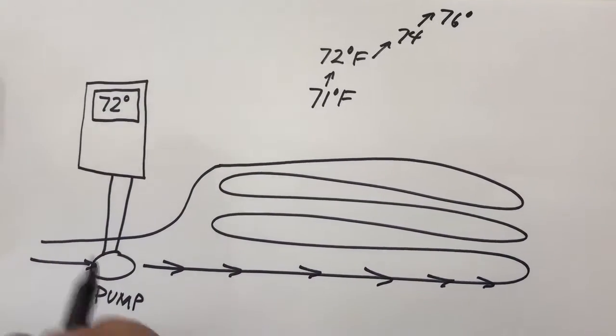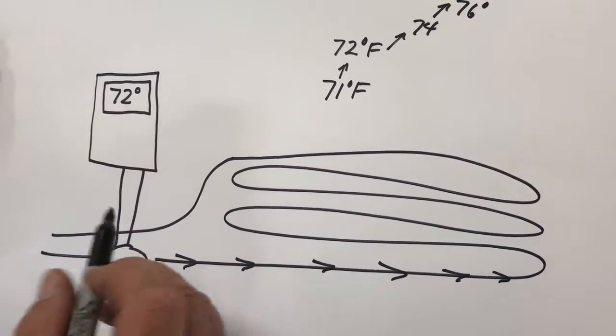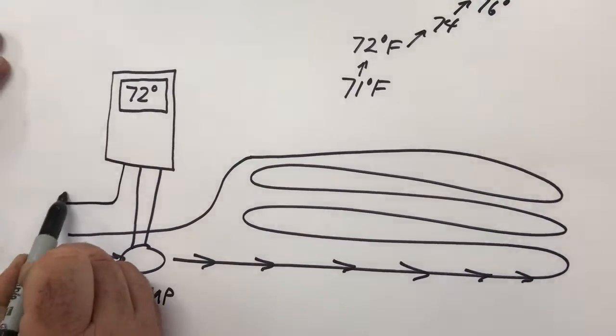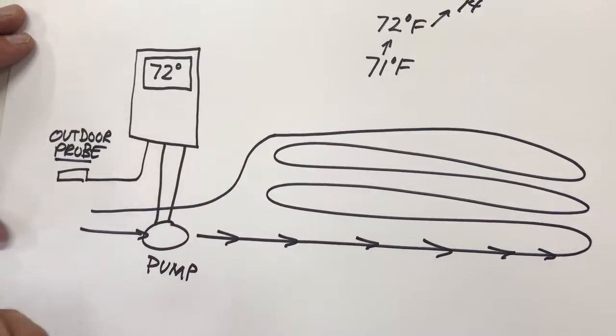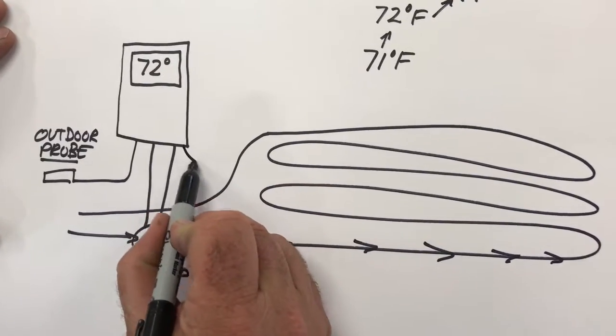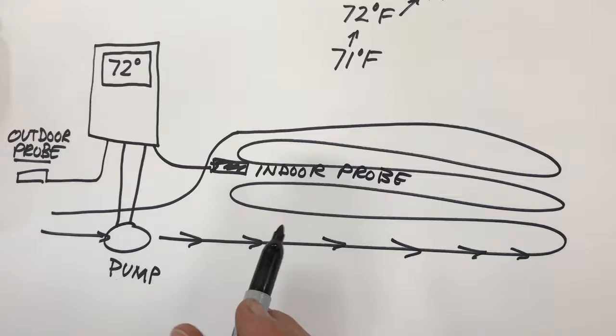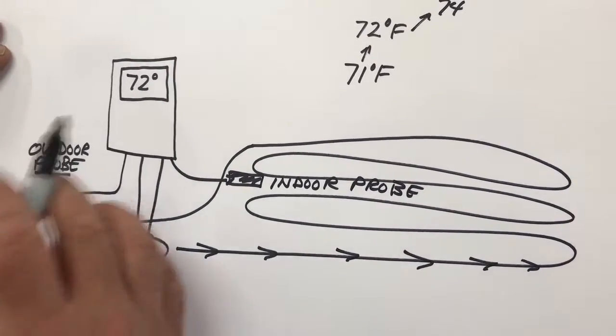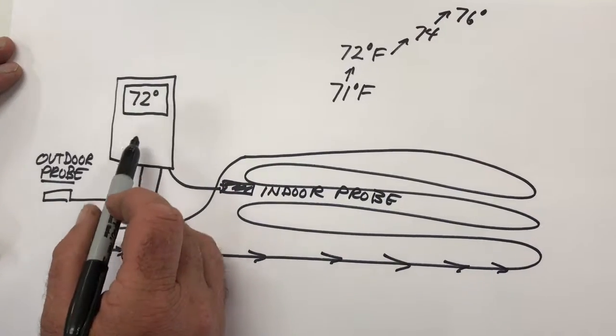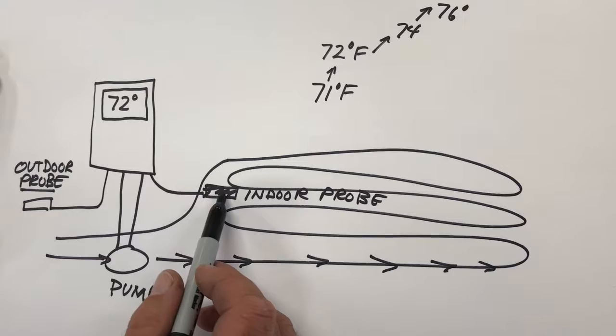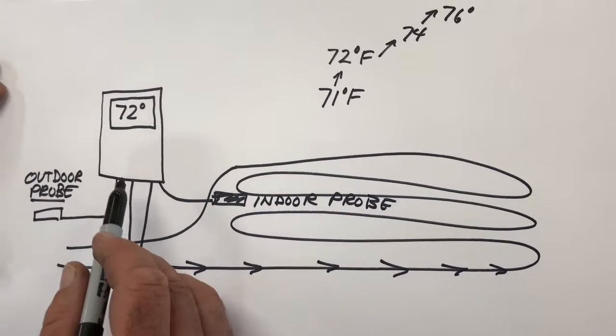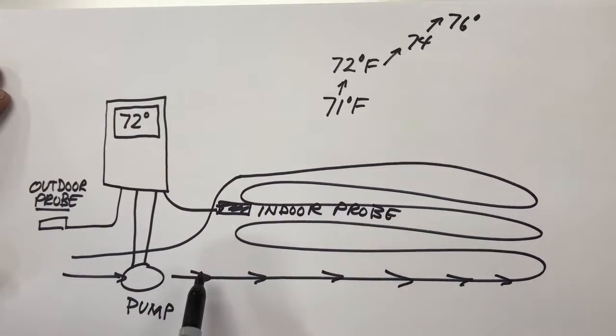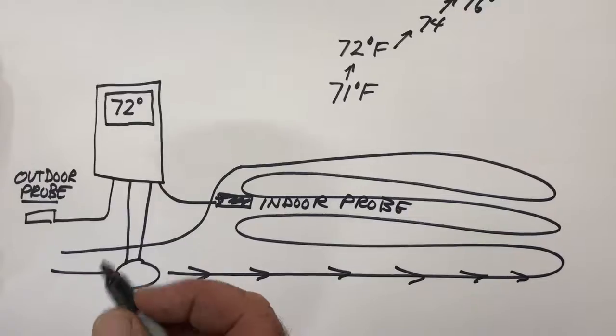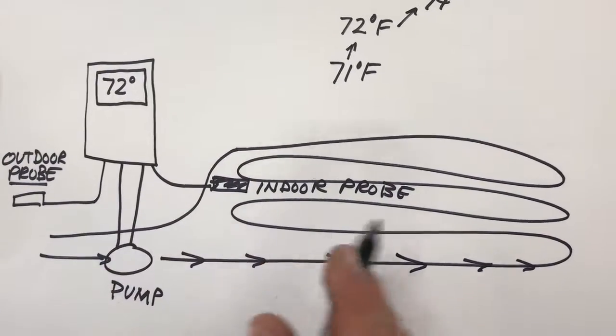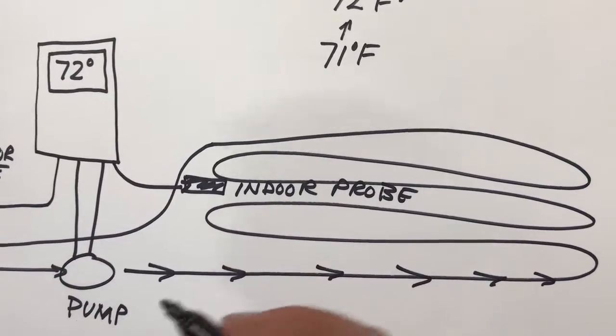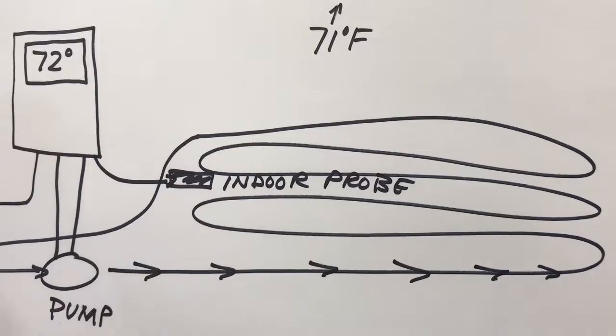So a smart system starts with what you see here, but it adds two things. First of all, it adds an outdoor probe that measures the outside temperature. It also has an indoor probe, which in this case would be installed in the floor. So what a smart thermostat system can do is make note of the outdoor temperature, make note of the floor temperature, and also note how much heat the whole room loses. And it will anticipate the heat requirements of the room, and it comes to know how much this particular installation tends to overshoot the set point temperature given an outdoor temperature.